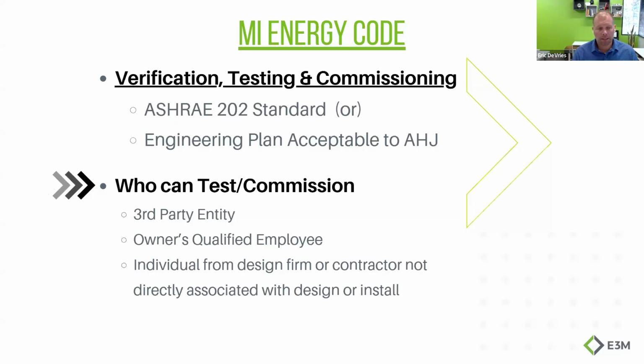The best example of this, from talking with Colorado and a couple other professionals, is a boiler project at a college where the college has a certified boiler operator on staff who runs and manages that boiler plant every day. The contractor can come in, do the retrofit, install the new boiler system, and then the owner's qualified employee—that boiler operator—can run the system through its paces and verify that it's working.